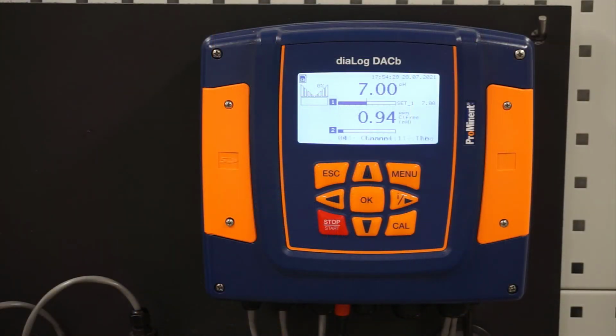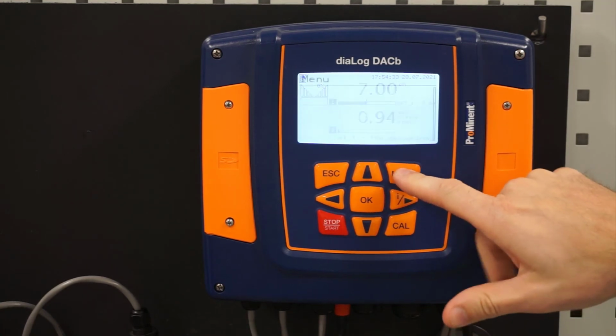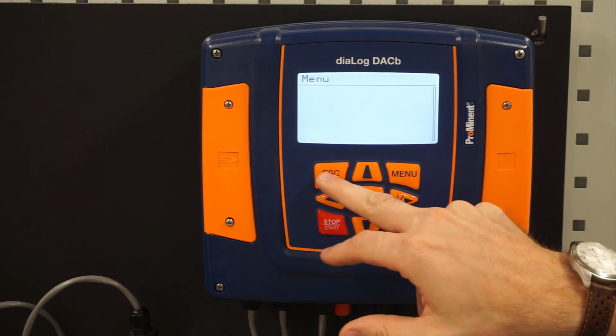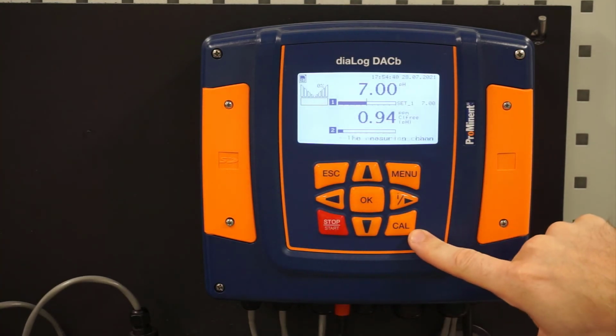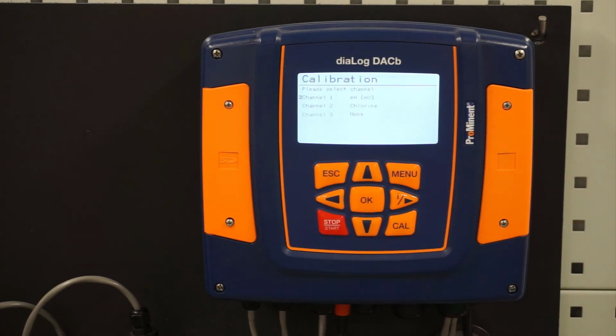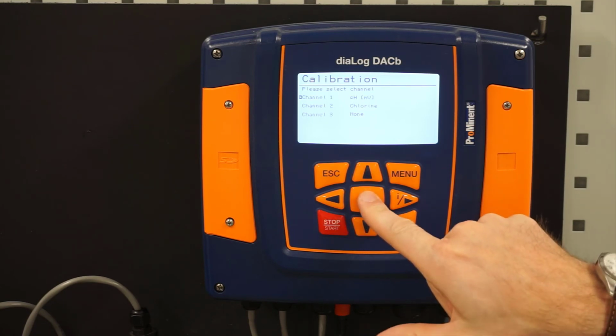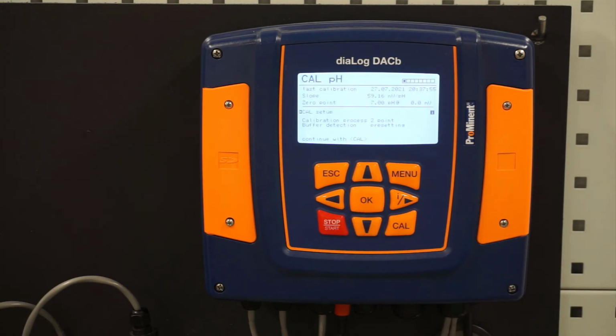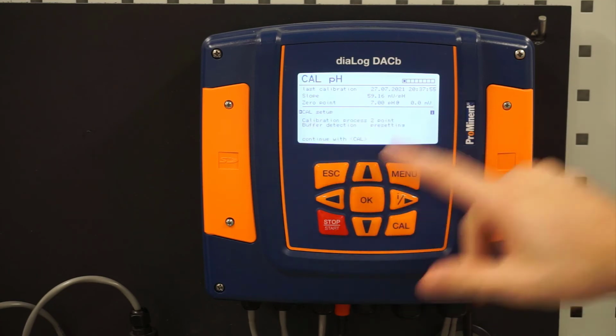Now that we're ready to do our calibration, we can access that in 2 different ways. We can either use the menu key and go to the calibration screen, or I can exit out and we have a shortcut key here that takes us directly to the calibration. When we're doing free chlorine, the pH is extremely important to the free chlorine reading. So we're going to want to calibrate our pH first. So we're going to go to channel 1, hit OK, and this will walk us through the steps of how to do a calibration.